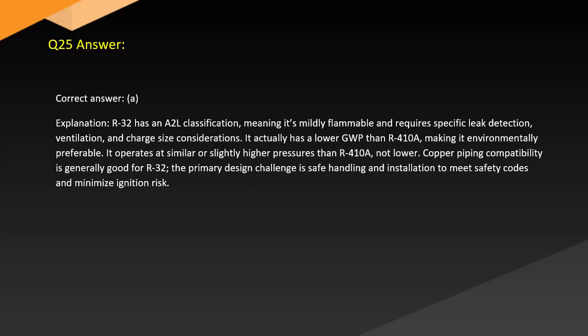Answer. Correct answer. A. Explanation. R32 has an A2L classification, meaning it's mildly flammable and requires specific leak detection, ventilation, and charge size considerations. It actually has lower GWP than R410A, making it environmentally preferable. It operates at similar or slightly higher pressures than R410A, not lower. Copper piping compatibility is generally good for R32. The design challenge is safe handling and installation to meet safety codes and minimize ignition risk.